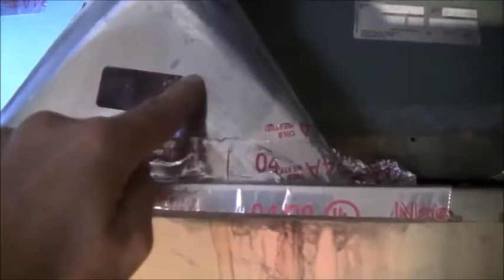You do not want to drill into this drain pan. That is going to cause you leaking water. So you can't just drill holes in this thing wherever you want. You could hit the drain pan, you could hit the coil, you could hit something you did not want to hit. So what I did was take these 2 screws out and bent this back. I left this hood in place, and then felt with my finger, and I could tell that the drain pan started right here. So by drilling here, I was below the drain pan, but in the airstream. So I was safe to make that drill hole right there.